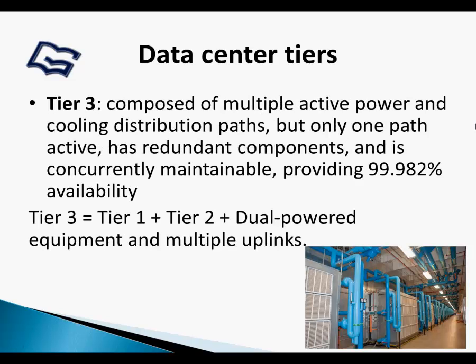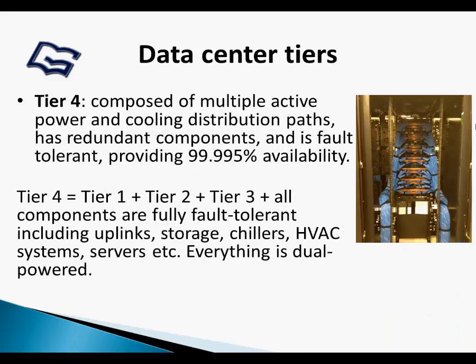Tier 3 is composed of multiple active power and cooling distribution paths, but only one path active, has redundant components, and is concurrently maintainable, providing 99.982% availability. Tier 4 is composed of multiple active power and cooling distribution paths, has redundant components, and is fault-tolerant, providing 99.995% availability.